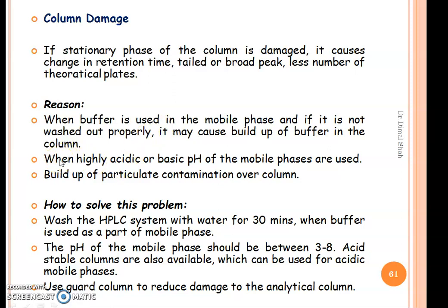Another reason is when highly acidic or basic pH of the mobile phase is used, it may damage the column and the column packing material can be removed. Another reason is build-up of particulate contamination over the column. Now, how to solve this problem?